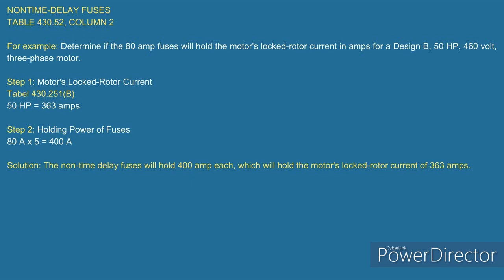Now, look at this. What I'm going to do is determine if 80 amp fuses will hold the motor's locked rotor current in amps. And this is a design B, 50 horsepower, 460 volt, three phase motor. As we just looked at in table 430.251B, the 50 horsepower was good for what? 363 amps. Now look at this. We tell you a non-time delay fuse will hold about 5 times, 500%. So if I take those 80 amp fuses at 5 times, look there, the holding power of that fuse is 400 amps, which will hold the locked rotor current of that motor at 363 amps.